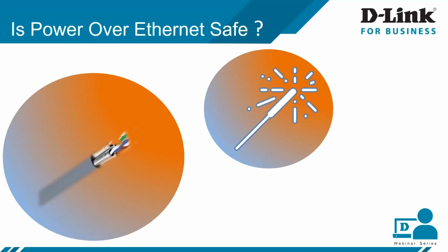Then why is there always a but? If PoE is safe, then why was it addressed in the NEC for power levels above 60 watts? The answer is there could still be a potential hazard caused by heat being generated by PoE within the cable bundle, which can cause insertion loss and cable degradation over a period of time, preventing proper data transmission. With everything from phones and security devices to life safety systems being powered over the network, loss of signal is a direct threat to life safety.